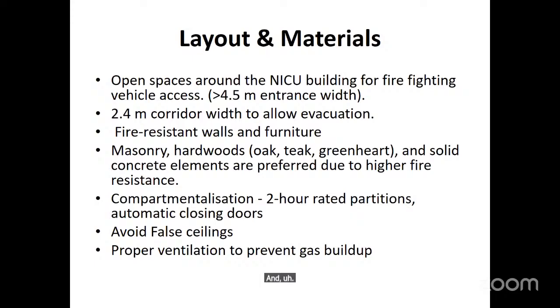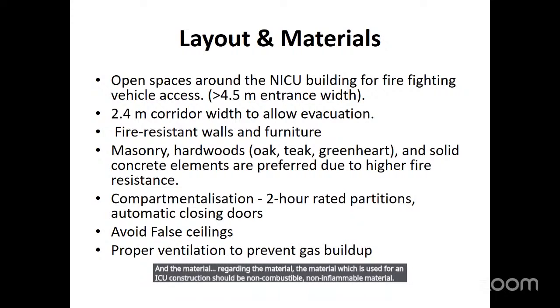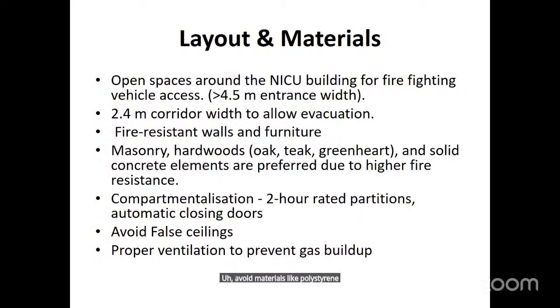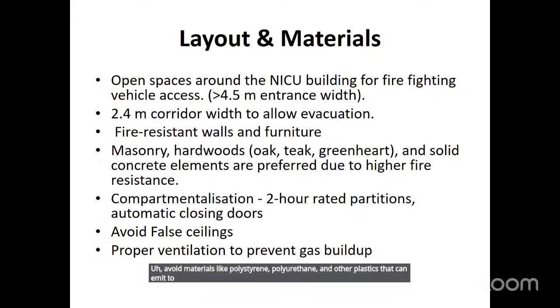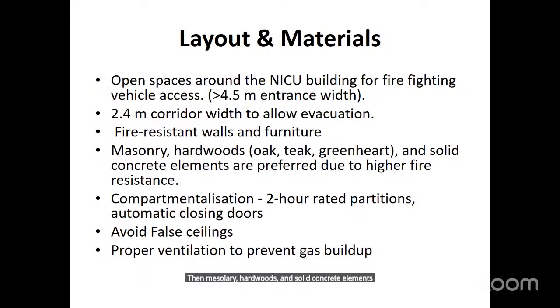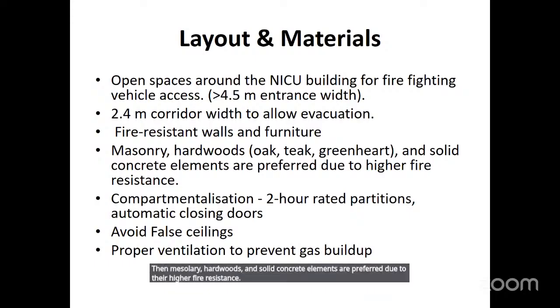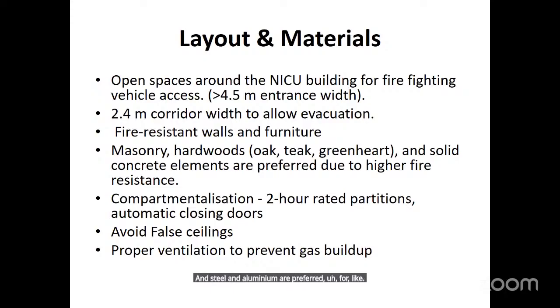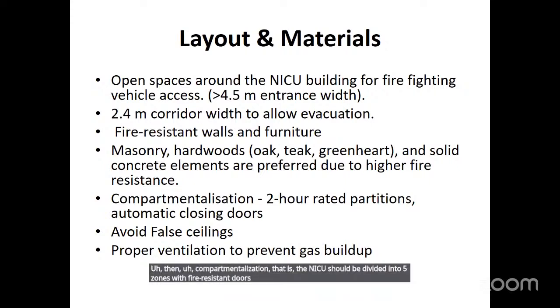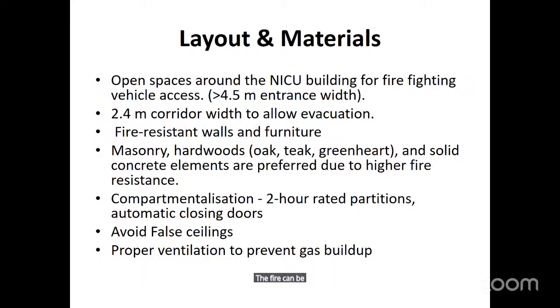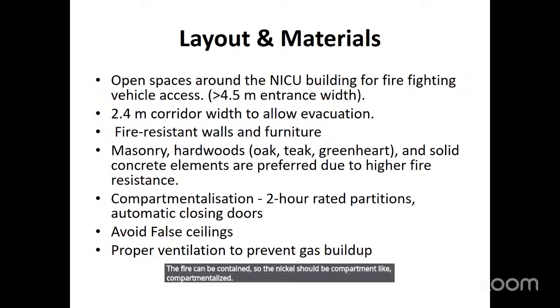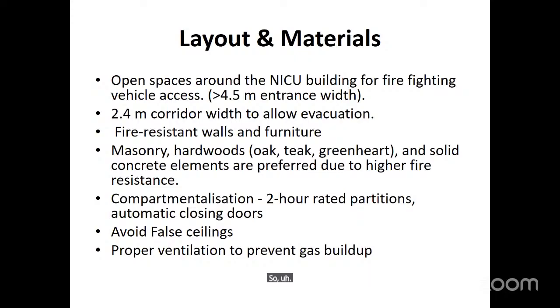Regarding the material used for NICU construction, it should be non-combustible, non-inflammable material. Avoid materials like polystyrene, polyurethane, and other plastics that can emit toxic fumes. Masonry, hardwoods, and solid concrete elements are preferred due to their higher fire resistance, and steel and aluminium are preferred for building units and compartments. Then compartmentalization: the NICU should be divided into fire zones with fire resistant doors to contain the fire spread. In case of fire, the fire can be contained, so the NICU should be compartmentalized. We can do this by creating partitions between the NICU units only. So, a 2-hour rated fire partition should be built.